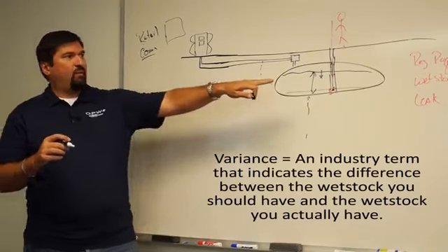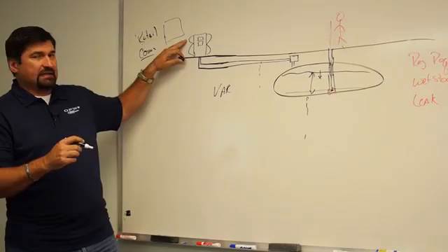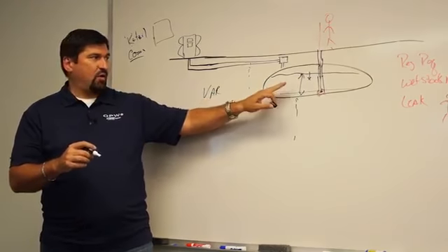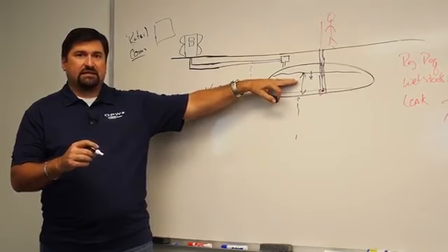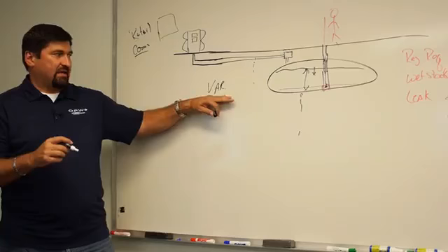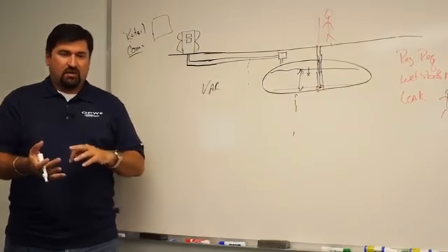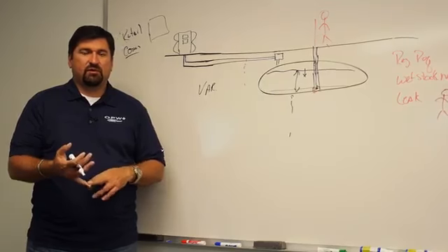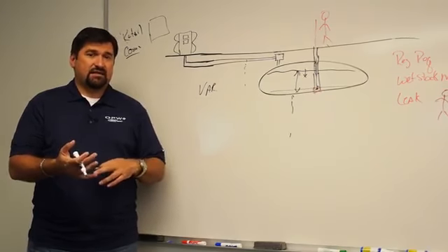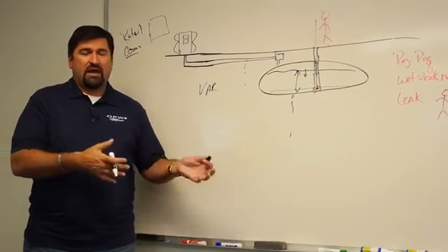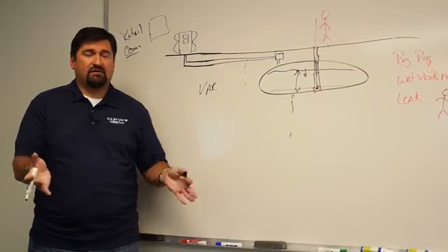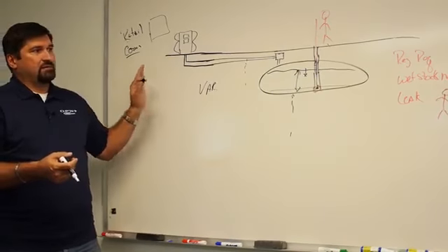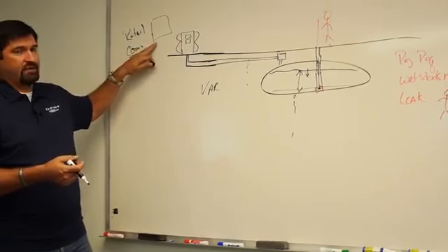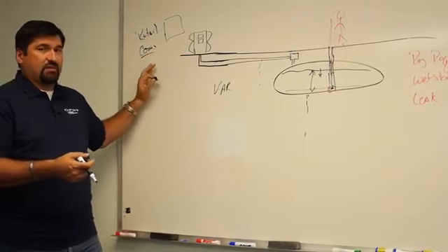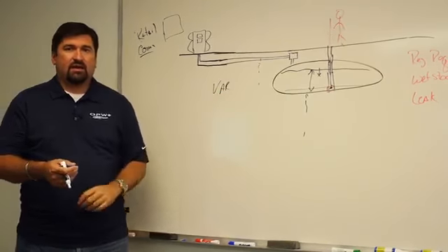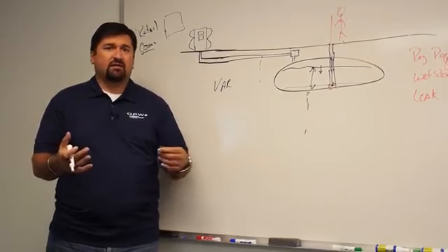And this is where people look at wet stock management: looking at everything that left the dispenser, what was dispensed from the tank, what was delivered back to the tank, and what's physically left at the end of the day, and coming up with a variance. Now this is where you start looking at regulatory requirements as well, because most states will tell you that you can have 1% of your throughput plus or minus 130 gallons, or some states say that you can have 0.5% with no overage, but you have to reconcile every 7 days, 10 days, 15 days, or every 30-day calendar month. But this is what an ATG will do for you. It will get you into your retail, your commercial, industrial, as well as your multi-use sites, but it's basically looking at the amount of product that is being dispensed and helping the end user reconcile his product level in the tank.